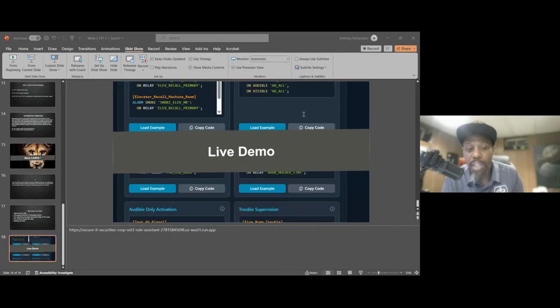You have your central station messages. You have your plus, which will send the signal, and your negative, which will send the restore. So you have your activation and your restore. Switch activation, you could do switch or just SW. This is all for the input side if you're using it for the switch. And then you have relay configuration. You would use relay configuration usually for dampers. When the relay goes active, it will send a confirmation, so you can take that confirmation and then either do something else with it or turn something else on. You would usually take that relay confirmation and then control either fans or some dampers after that.